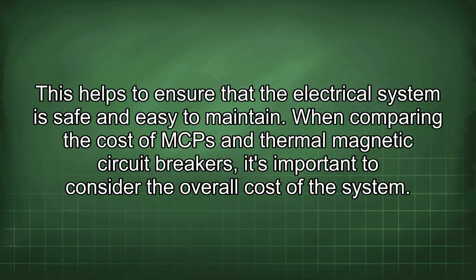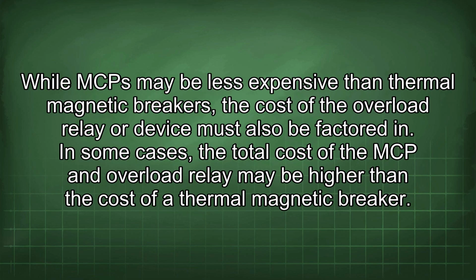When comparing the cost of MCP and thermal magnetic circuit breakers, it's important to consider the overall cost of the system. While MCP may be less expensive than thermal magnetic breakers, the cost of the overload relay or device must also be factored in.